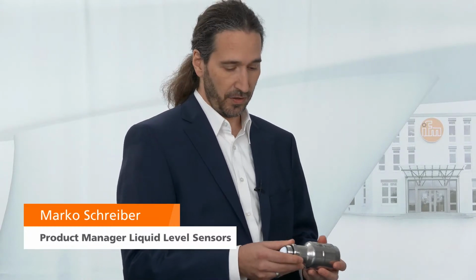80 gigahertz is very well known so far as a level measurement technique, and it has advantages compared to other frequencies in radar technology. The good thing with 80 gigahertz is that with this high frequency, you can set up a sensor with a very narrow beam angle and at the same time have a very small process connection. That means with lower frequencies you would need bigger process connections to get the same narrowness of the beam angle, and this has different advantages in the process industry.